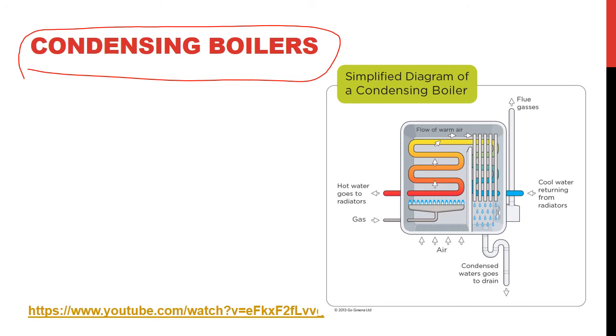So what happens here is all the flue gases undergo more heat extraction until the point where they start to condense, and the flue gas here will be let out at around 60 degrees Celsius. But the caveat is we will have some condensation here.